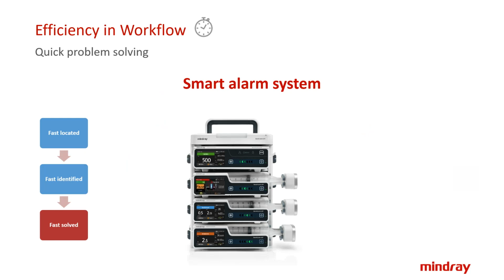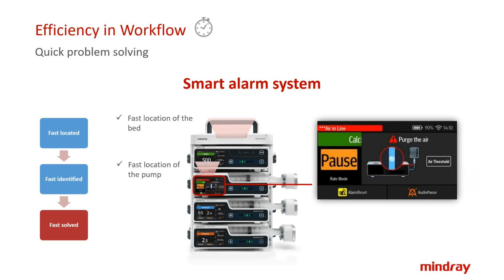And then we provide the smart alarm system on the E-Series, including fast location, fast identification, and fast display. First, for fast location, you can see there's an alarm light on the docking station, to tell you which docking station has triggered the alarm. We can also locate the pump by the alarm lamp on each pump. At the same time, an alarm message is displayed on the screen showing how to do the troubleshooting, and you can follow the graphic troubleshooting instructions to solve the problem very quickly.